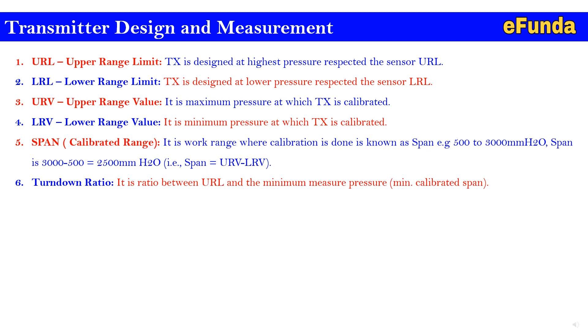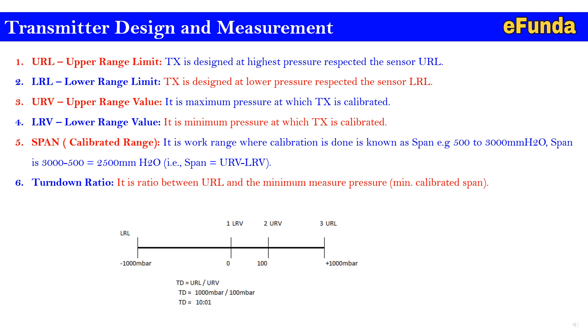Turndown ratio is the ratio between URL (Upper Range Limit) and the minimum calibrated span. One can refer to the sketch where LRL is minus 1000 millibar, LRV is 0, URV is 100 millibar, and URL is plus 1000 millibar. The turndown ratio is calculated as URL divided by URV.